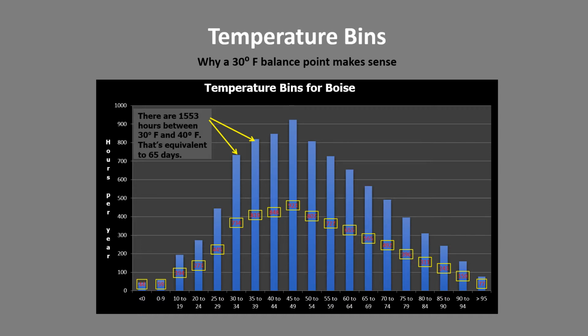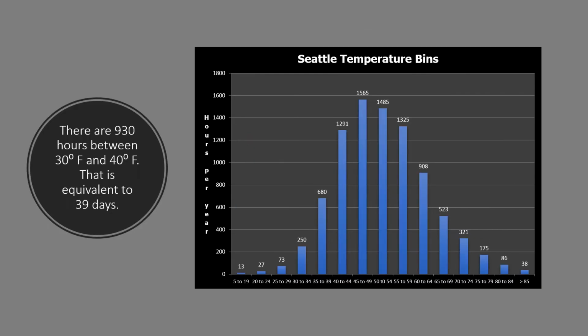So between 40 and 44 degrees in Boise, we have 848 hours a year. So if you drop the balance point between 40 all the way down to 30, that's 1,553 hours, or the equivalency of 65 days that strip heat would have to come on to help heat the house. And boy, that's a lot of electricity to do.